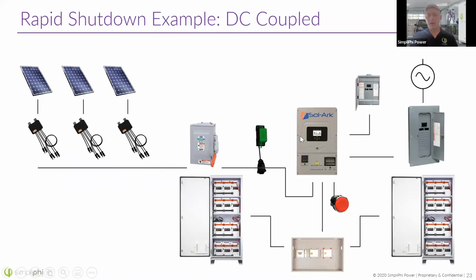As an example, a DC coupled system, you've almost always got a PV disconnect box in general, but maybe you've got the Tigo rapid shutdown attachments or the optimizers, so the TS4-F or similar, and you've got this button for shutting them down. This button is going to kill the power to the transmitter, and when the rapid shutdown modules don't see power from the transmitter, they're going to kill the PV array. This button is also going to disconnect the batteries right here and just turn off the inverter in general and shut it down.